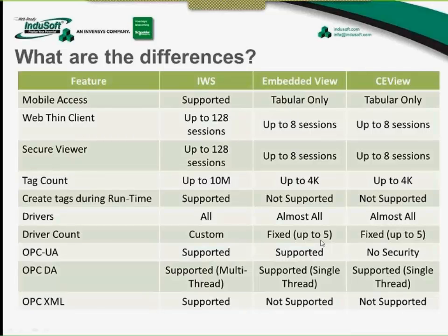So when you are going into Embedded View and CE View, you don't have that capability. If you're using only one OPC server or two, and they're always online or on the same computer, not remote, this doesn't matter much. But if you're using an OPC server remotely, and that connection goes down, it is important for you to have that independence. Then you want to go with InduSoft Web Studio.